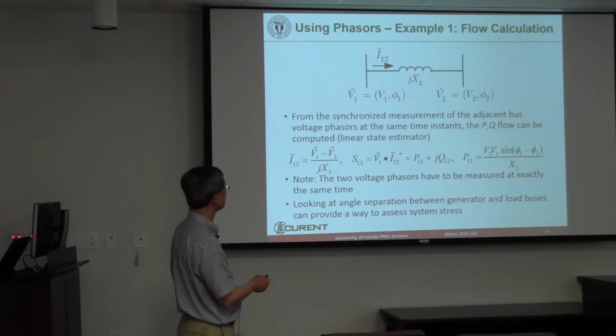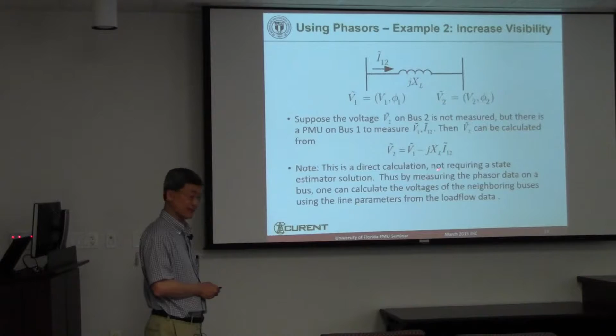The other, more common option is that if you put a PMU on this bus, in addition to the voltage phasor, you measure all the currents going out. Using this voltage phasor and this current phasor, you can calculate V2 — you make the next bus observable. This isn't so easy when you just have an amplitude. This is a direct calculation of the next bus over, so it's not a state estimator solution — people call it the linear state estimator because it doesn't require iterations. This scheme works if you have very accurate phasor measurement units, which we found is still not quite the case.